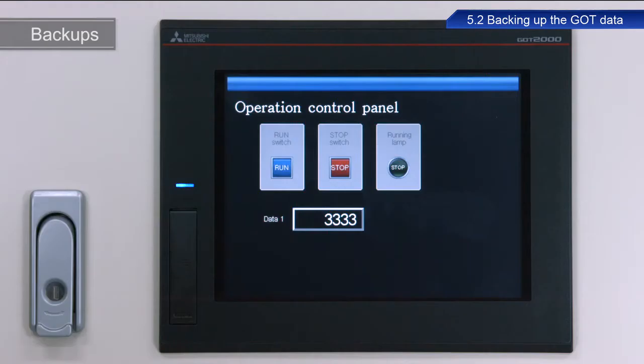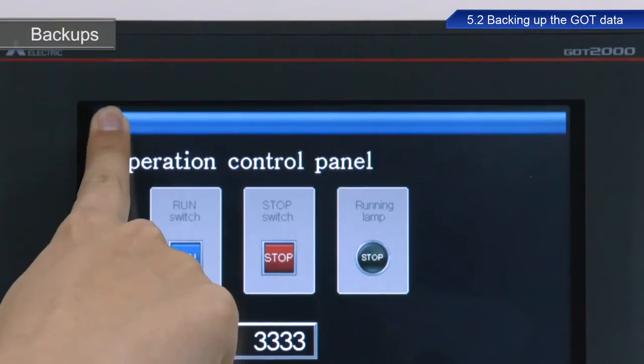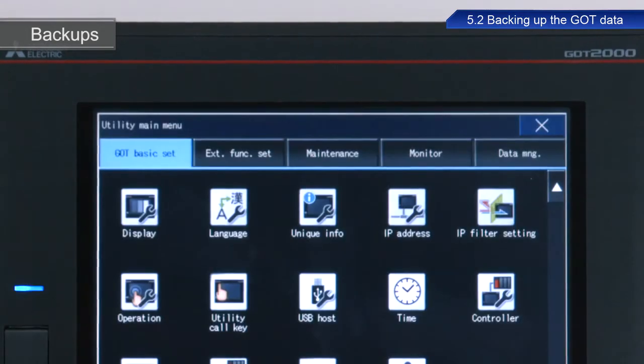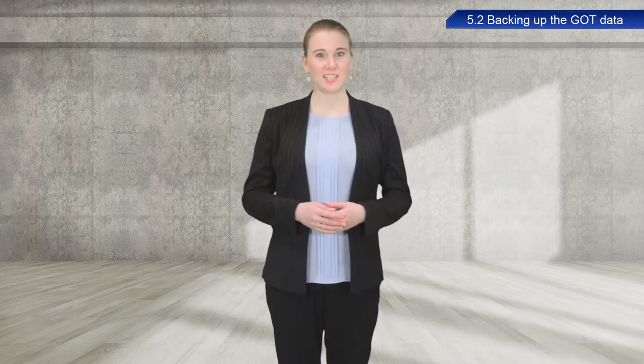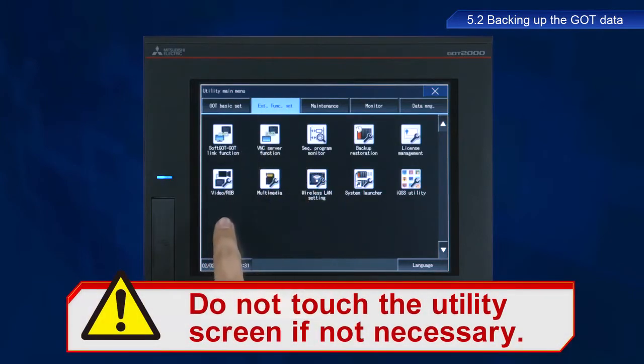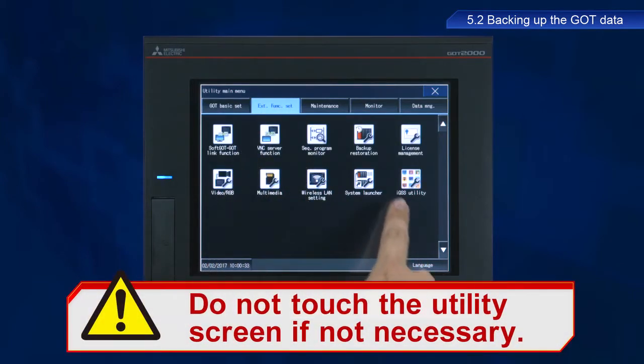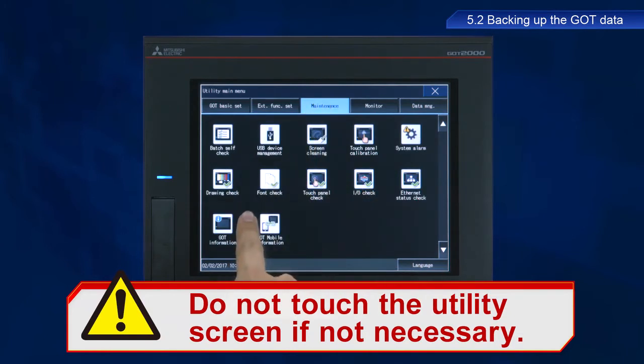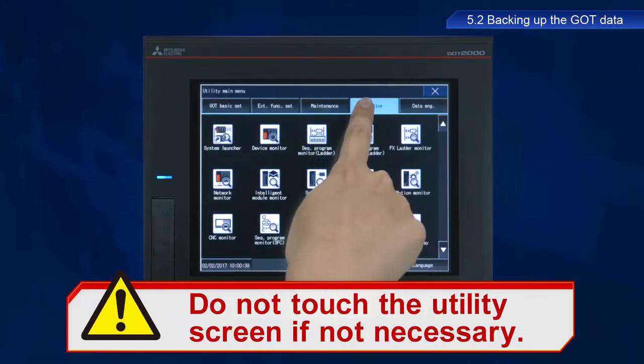I will now describe the procedure to backup data stored in the GOT. First, display the utility screen. If the device is configured with the factory default settings, press and hold the upper left part of the screen to display the utility screen. The display method can be changed if desired — refer to the product manual for more information. A single touch on the utility screen can change even important settings. Do not touch the screen except when necessary to perform the intended operations.